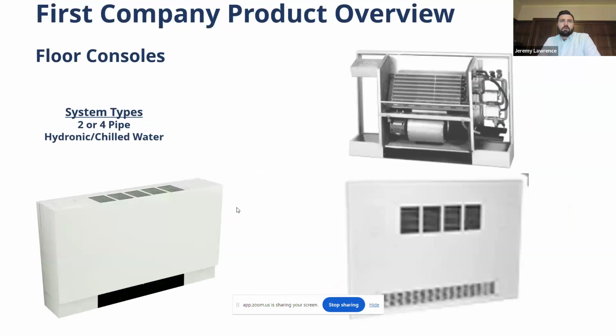Floor consoles, very common all over Ontario in institutional, commercial, and industrial systems. Either built into the wall or sitting off the wall. Hydronic heating and cooling are the only two options on these ones, and they can be either 2 or 4 pipe systems, meaning that they can either do heating and cooling seasonally, or the user has the choice depending on how the building is piped.